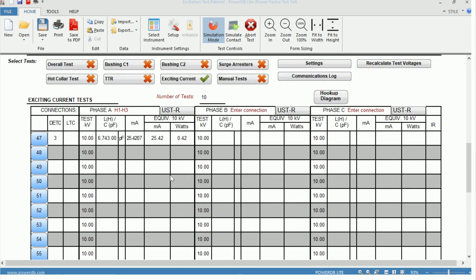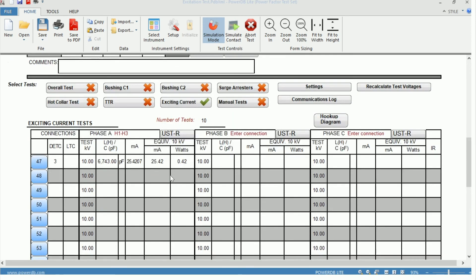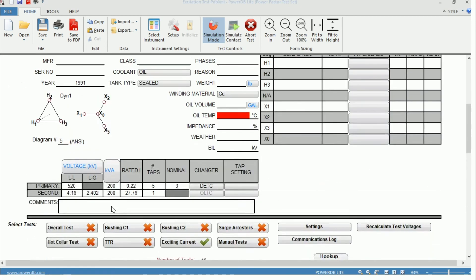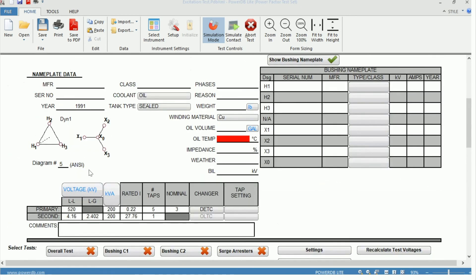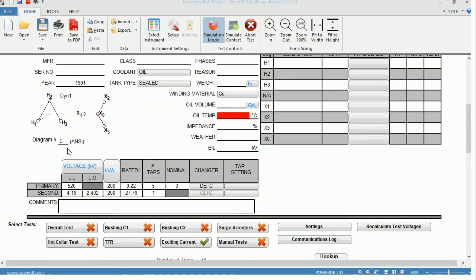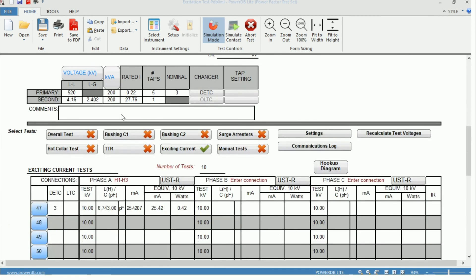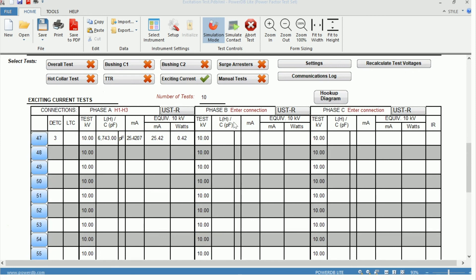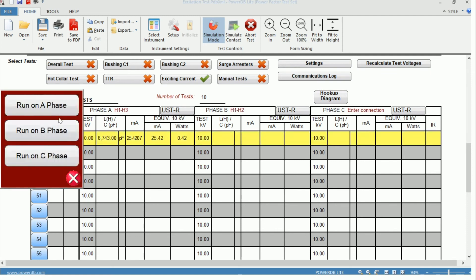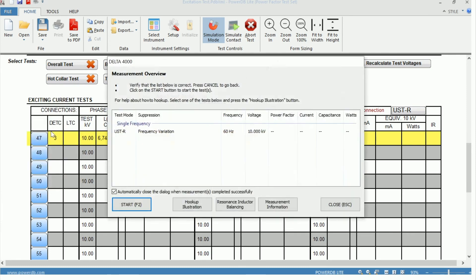Now that we've saved, we can move forward with another test as well. So if we were to test phase B, for instance, we can go back up to our vector diagram. B, in this case, would be H1, H2, corresponding to our X0, X2. So we can put in H1, H2. We already have our test voltage. So now we can click here again. Instead, we'll run on phase B.